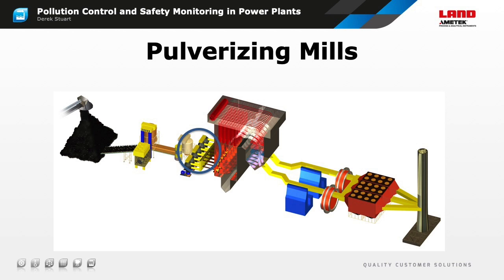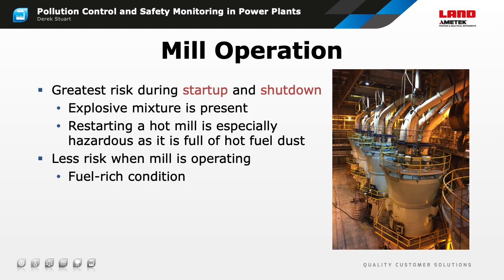The final area of concern in fuel handling is the mill or pulverizer, where the fuel is crushed to a fine powder before being fed to the burner. Mills are large and powerful devices, so a fire or explosion within the mill can cause significant damage and lost production. The greatest risk of fire or explosion comes during startup and shutdown, as this is when there is an explosive mixture of fuel and air within the mill. The risk is lower when it's in operation, as the coal dust concentration is generally above the upper explosive limit.